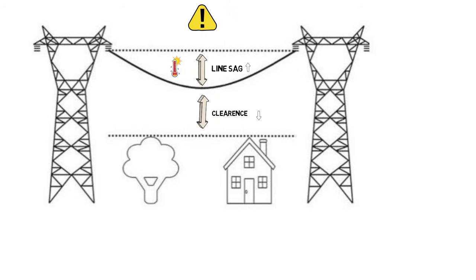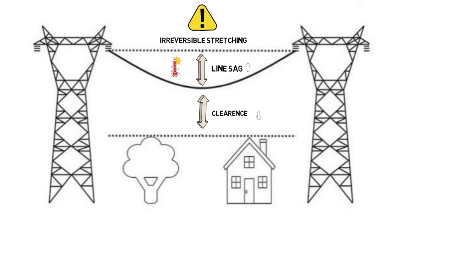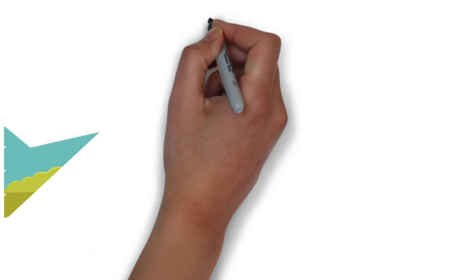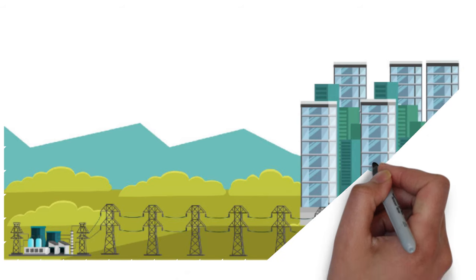This is more onerous at high temperatures which is likely to result in irreversible stretching of the transmission lines. The thermal limit is specified by the current carrying capacity and is available from the manufacturer's data.